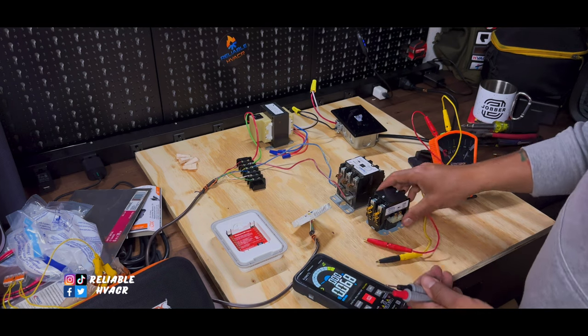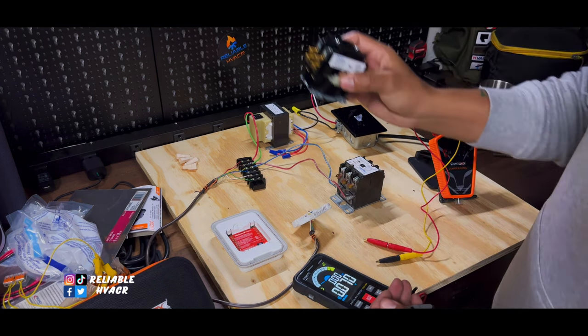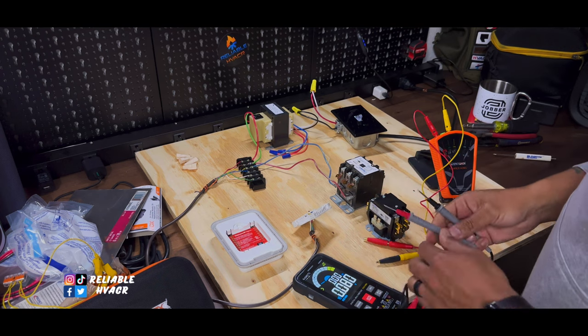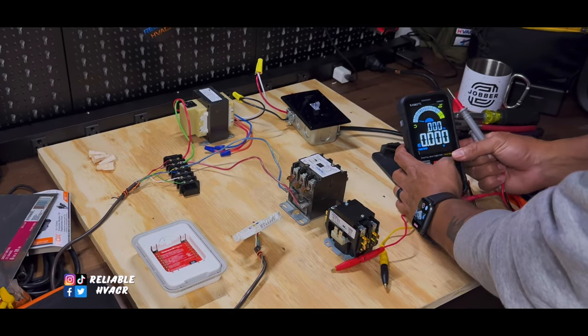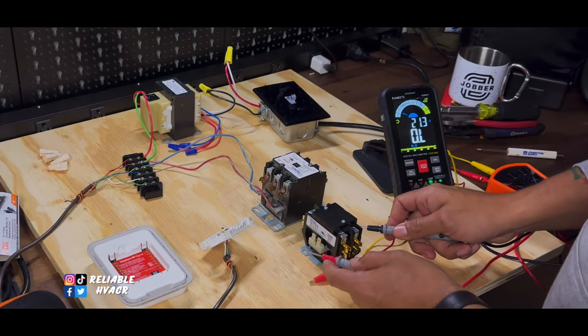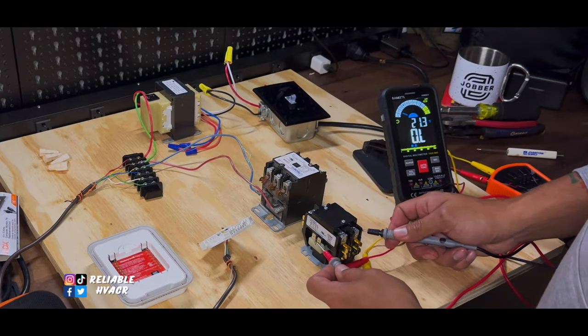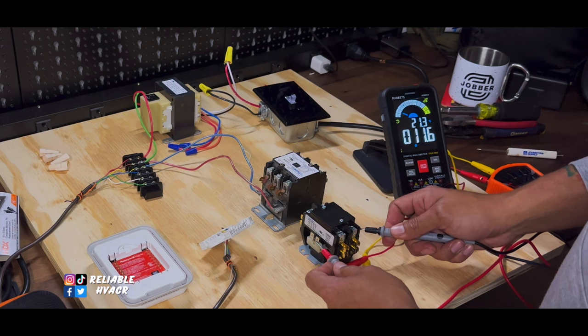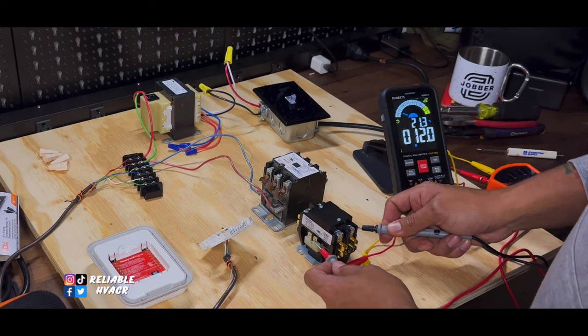If you have the coil, see on a two-pole like this, the coil might be on the sides. So, if you get a reading on either side, we're going to go with ohms. Okay, we got ohms there. If you take a reading across the coil, usually it's close to 13, this one's right at 12, that's fine.